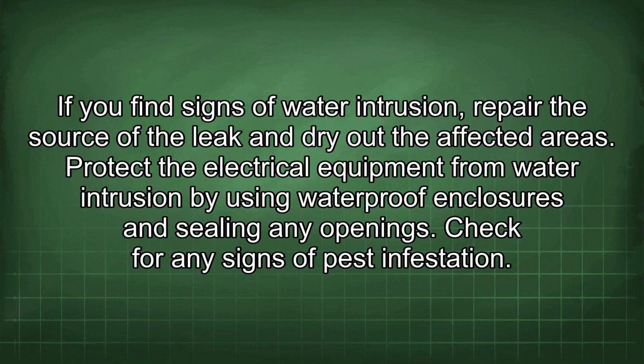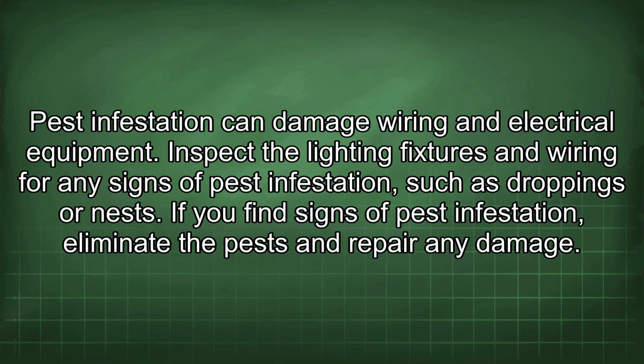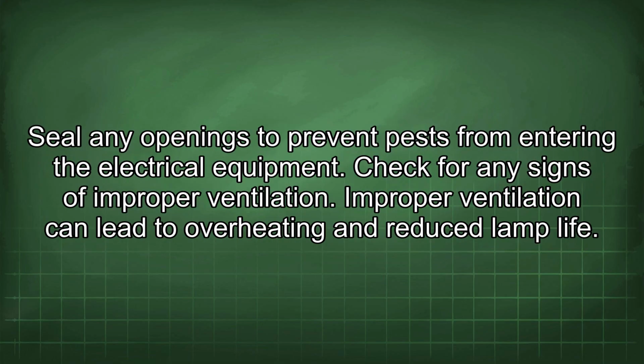Check for any signs of pest infestation. Pest infestation can damage wiring and electrical equipment. Inspect the lighting fixtures and wiring for any signs of pest infestation, such as droppings or nests. If you find signs of pest infestation, eliminate the pests and repair any damage. Seal any openings to prevent pests from entering the electrical equipment.